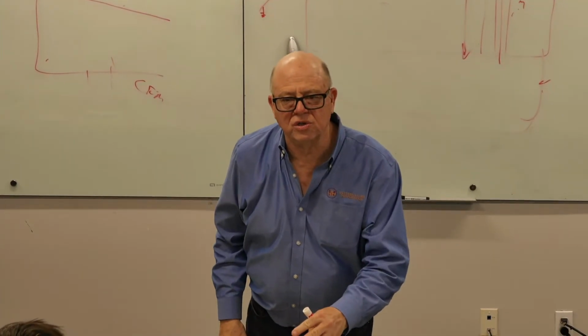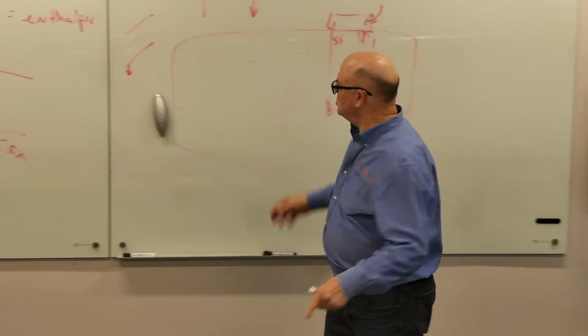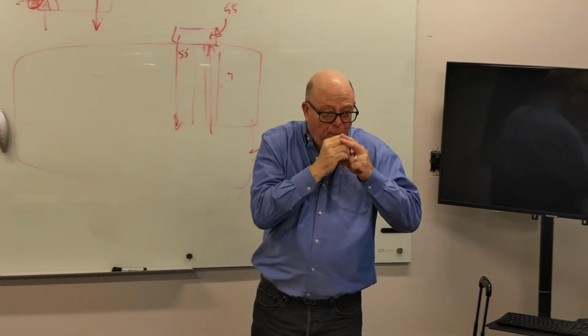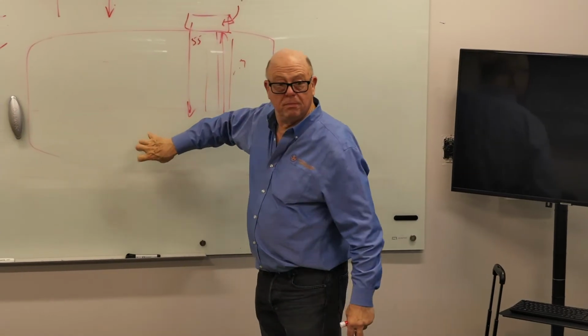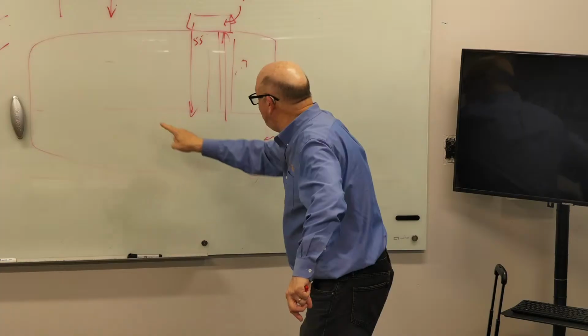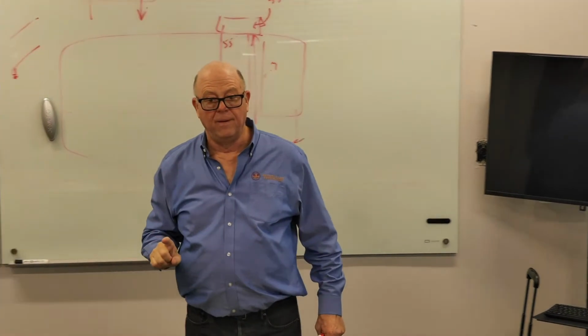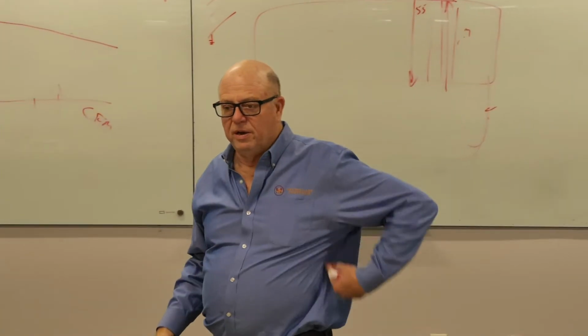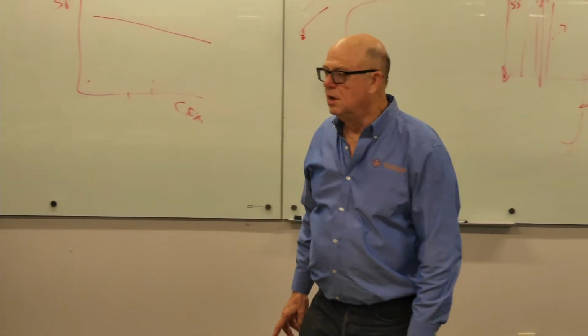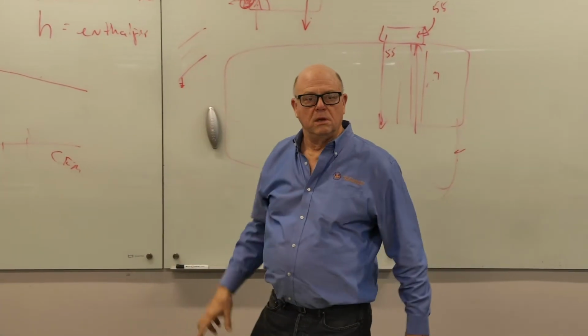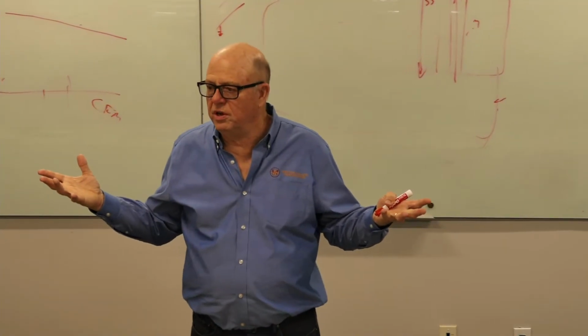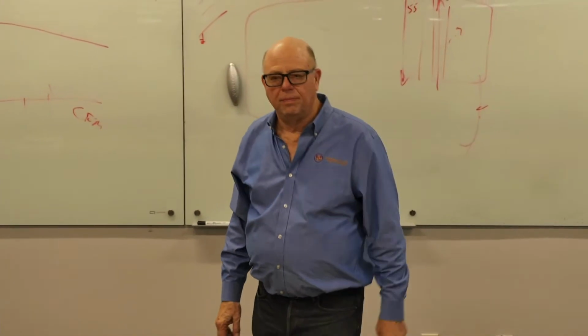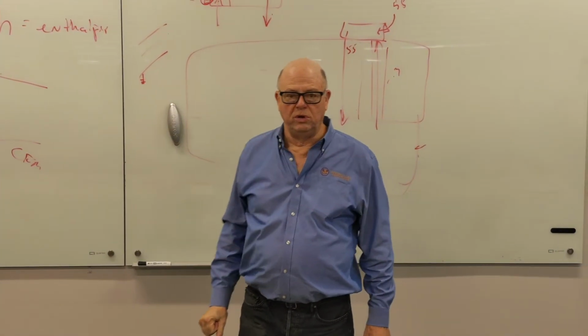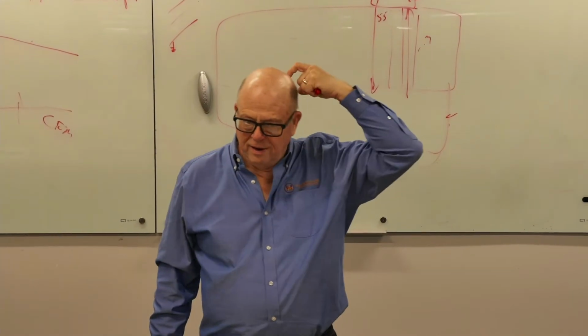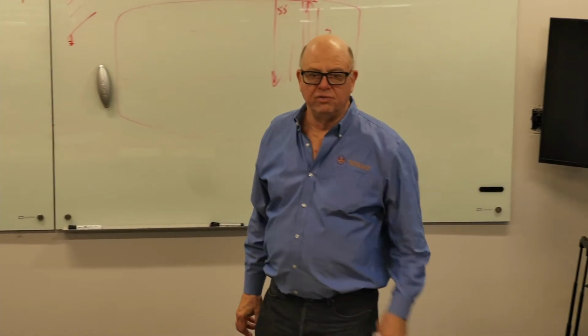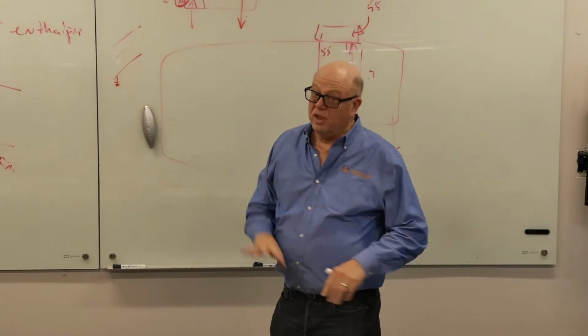So that actually works for a relief fan, because bear in mind, this air is a plastic paper bag. We're blowing up, we're adding static here. So there's some push to help the prop fan. And so, if we were standing here in the 70s, even the first half of the 80s, everybody would look at a propeller relief fan and they would say, that's great. If one of these was in operation, you could hear it 3 buildings away on the lot. They are louder than anything. So that was one problem. Another problem was they couldn't overcome very much static.